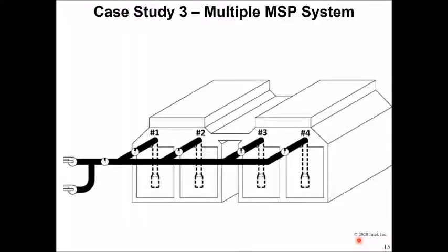This last case study is an Ingersoll Rand condenser. There are two condenser shells running at a common pressure. Each shell has two bundles, each with a dedicated air offtake line. This unit operates with 3 RheoVac probes. One probe is installed in the common, and the other 2 probes they allow to be moved between the 4 other vent line locations. For this leak audit, a 4th probe was installed and the common probe was moved so that each vent line 1 through 4 could be monitored.